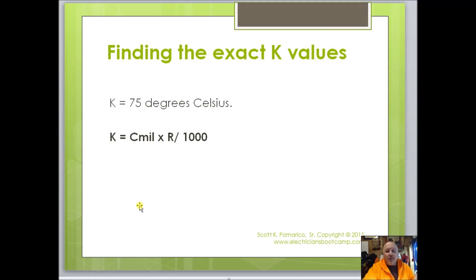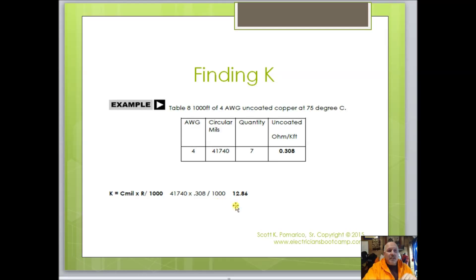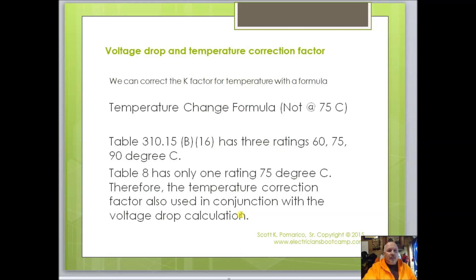To find exact K, the formula is: circular mils (from Table 8) × resistance (from Table 8) ÷ 1000. If they give you a specific wire type, you can find exact K. If they just say 'number 8 wire,' use 12.9 for copper or 21.2 for aluminum. For example, for number 4 wire: 41,740 (circular mils) × 0.308 (ohms per thousand feet) ÷ 1000 = 12.86, which is essentially 12.9.